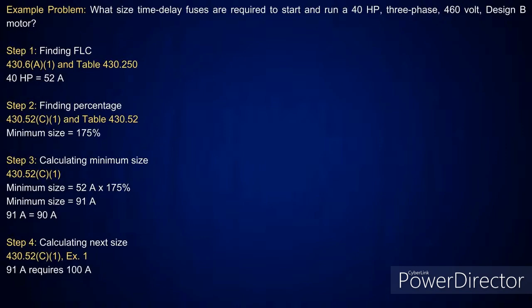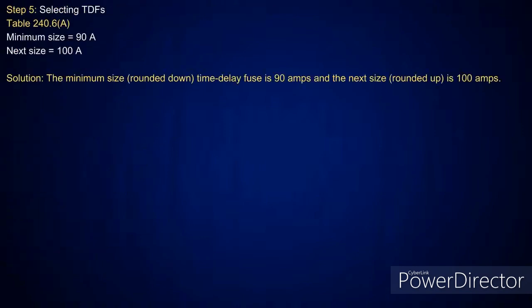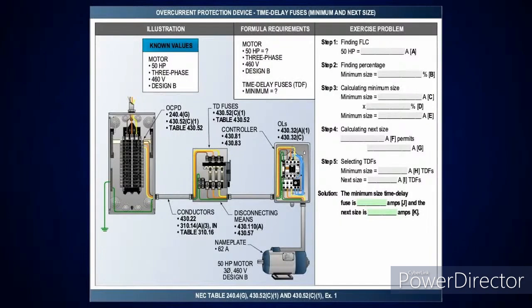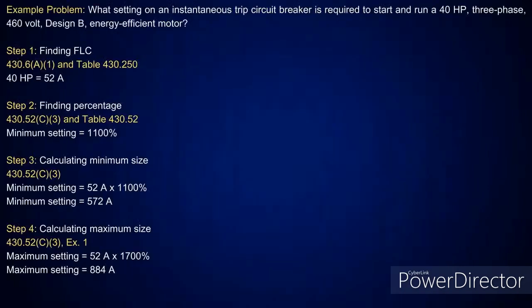Okay? Now, you're going to notice, even when you come in and you do your exercise problems, I want you to look here. I'm using the same motor here. I don't want you just going all over the place. When I get to this motor right here, I know it's 65 amps. I'm going to do the same calculation. If I'm doing the non-time delay fuse, I'm going to do it at 300%. Here, time delay, I'm going to do it at 175. So everybody should be able to do this pretty easily if they're just following along, paying attention here. Now, you guys should be able to go back to that illustration real quick.